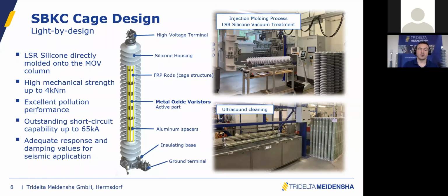So in the polymer family, we have the cage design. Probably many people are familiar with this design, first of all because it's competitive. It's a cost-effective solution. It's light, and it also offers a lot of technical advantages, up to 400 kV system. Depending on your mechanical requirements, it's possible to use the cage design. The ratio between weight and mechanical strength is quite interesting, and of course it has excellent pollution performance, which comes from the properties of the silicone material.